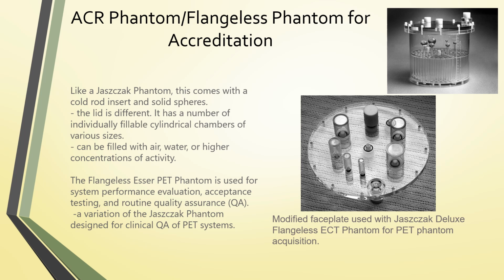So like the Jaszczak Phantom, the flangeless Phantom comes with cold rod insert and solid spheres. The lid is a little bit different. It has a number of individually filled cylindrical chambers of various sizes, and it can be filled with air, water, or higher concentrations of activity. The flangeless ESSER PET Phantom is used for system performance evaluation, acceptance testing, and routine quality assurance. And this is a variation of the Jaszczak Phantom that's designed for clinical quality assurance of PET systems.